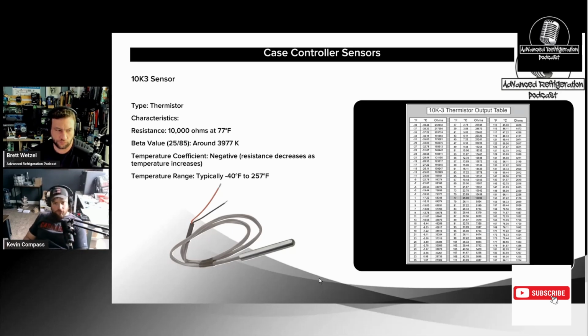If I have ohms and it's close to what the case temperature is, then I know I have a cable issue. So at that point, I will disconnect the cable and check the sensor again. If the sensor is good, I will twist the cable together and go back upstairs in the rack room, or wherever the board is, and put my meter on ohms and check that. I should have a closed signal, zero ohms, at that board point with it disconnected. And that would tell you your wire's good.